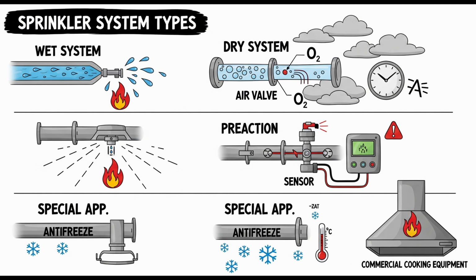NFPA 13 provides the sprinkler requirements when sprinklers are used as part of that protection. The source also reminds us, logically, that any sprinklers or nozzles located in ducts that might pass through unheated areas, like an attic or outside wall, and are subject to freezing temperatures must be protected against freezing, for example, using dry pendant sprinklers. Makes sense. Even in a generally hot kitchen duct, parts of it could be exposed to cold.